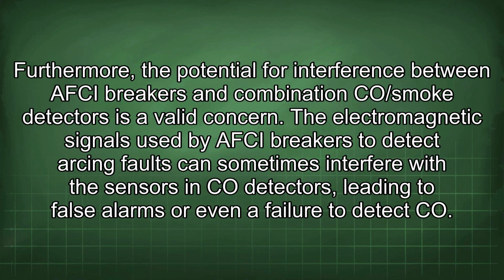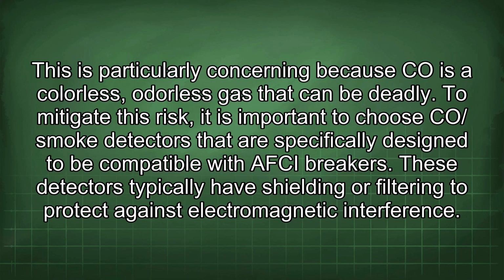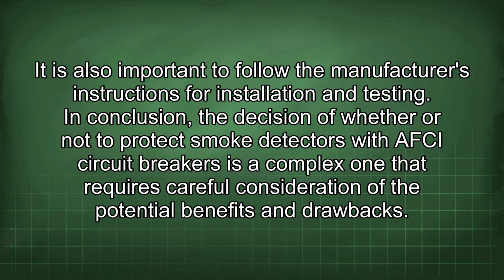Furthermore, the potential for interference between AFCI breakers and combination CO/smoke detectors is a valid concern. The electromagnetic signals used by AFCI breakers to detect arcing faults can sometimes interfere with the sensors in CO detectors, leading to false alarms or even a failure to detect CO. This is particularly concerning because CO is a colorless, odorless gas that can be deadly. To mitigate this risk, it is important to choose CO/smoke detectors that are specifically designed to be compatible with AFCI breakers. These detectors typically have shielding or filtering to protect against electromagnetic interference. It is also important to follow the manufacturer's instructions for installation and testing.